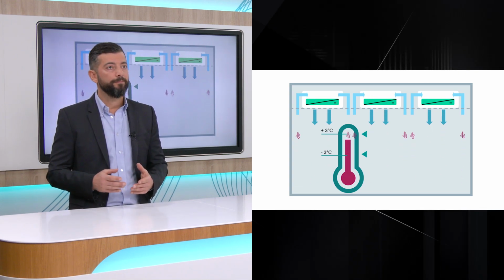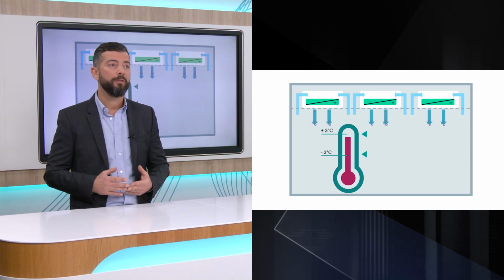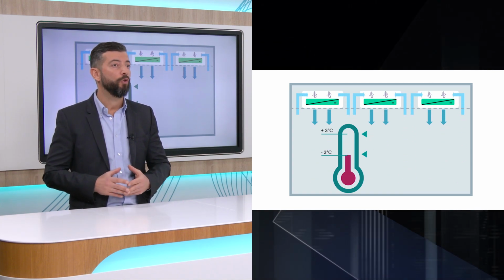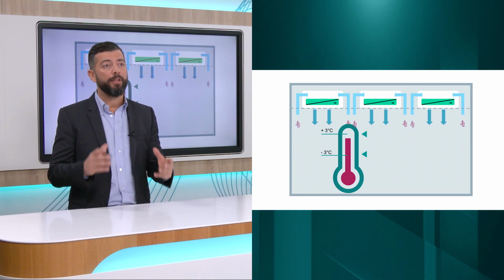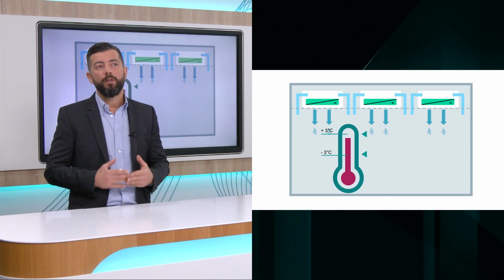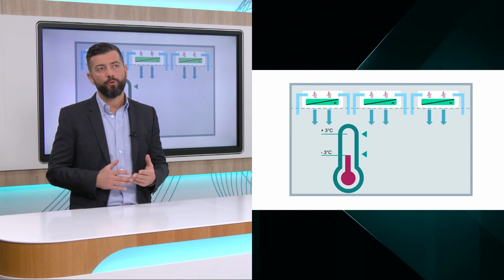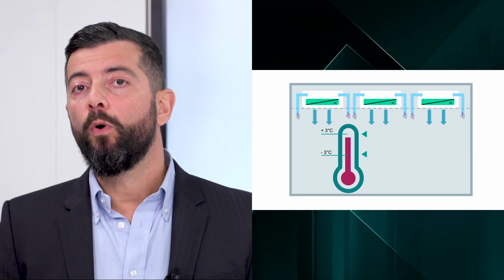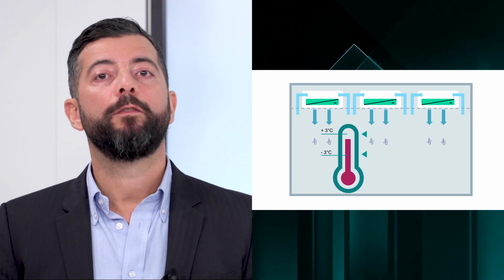In order to make sure the right acceptable flow tolerances are taken into account, it is essential that the HVAC designer specify these tolerances by taking into account the sensitivity of the units they are looking to use within the application under design. When you look at passive units, like radiators, radiant panels, or even passive chilled beams, there is no necessity for accurate regulation of water flow rates, and it is normally accepted to just make sure the return temperature is within acceptable limits of plus or minus 2 or 3 degrees, for example.